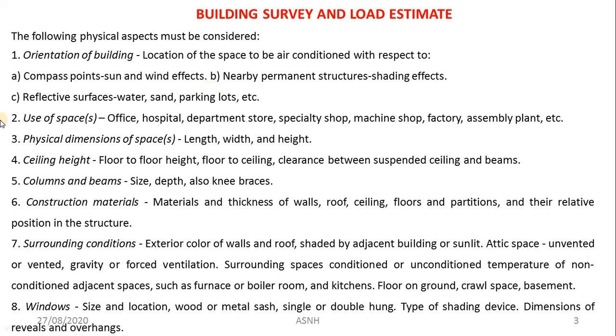Surrounding conditions are also most important and are available from Carrier charts and ISHRAE/ASHRAE standard guideline books. Surrounding conditions include the exterior color of the wall and roof, whether shaded by adjacent buildings or in sunlight, attic space conditions (unvented and vented cavities), and gravity or forced ventilation. We must consider surrounding conditions in order to avoid losses.